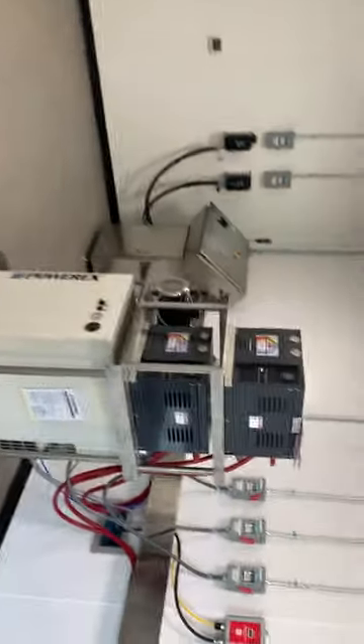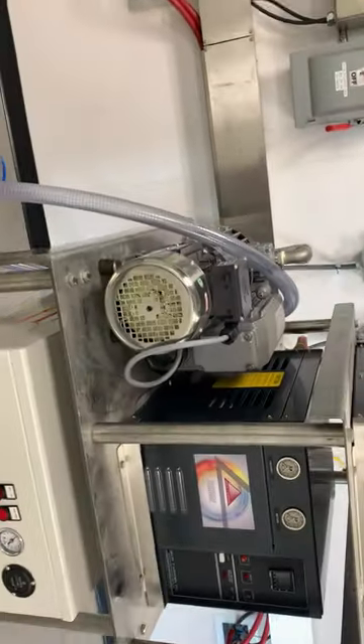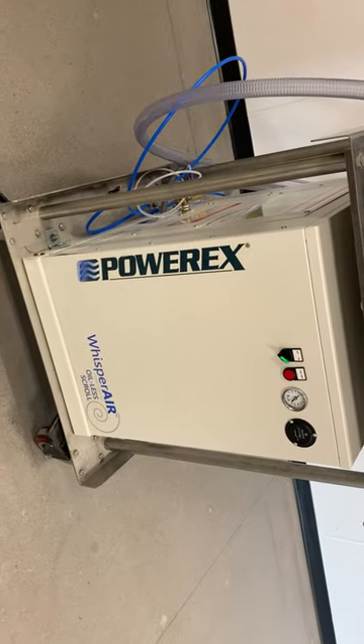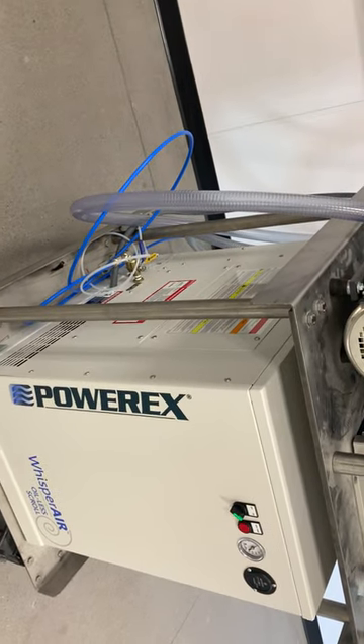This is where the PLC is normally located, but this particular customer wanted a remote touchscreen on the other side of the room. We have a roof-mounted water-cooled chiller that cools the main negative 60 degree chillers located in the PLC room — so it's not an air-cooled system and doesn't dump heat into your room. The chillers are located here, and we've got two Delta T heater systems for the heating circuits, a high vacuum pump to reach low pressures, and an oilless five-horsepower compressor for purging the system and activating valves.